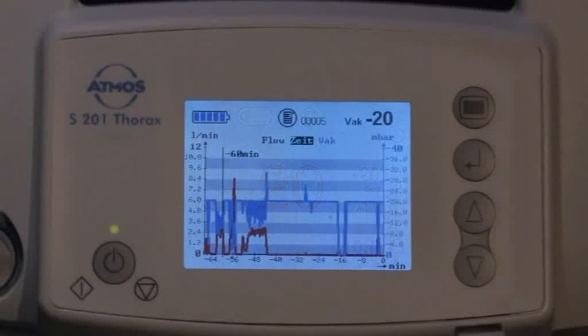The integrated therapy monitoring system shows on the display at the push of a button the progression of therapy from 30 minutes up to 12 days. The treatment success can be checked at any time and signalizes when the drainage can be stopped. Thus, time-consuming and cost-intensive x-ray controls which put the patient through unnecessary strain can be reduced.